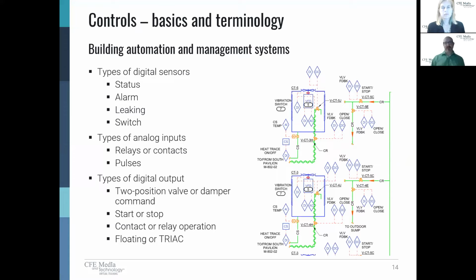It is a contact closure. Now, that's very common within our building automation system to use a variety of digital signals, a lot of digital inputs, a lot of digital outputs. On or off, yes or no. We're going to communicate with external systems with relays. But in addition, we can control solenoid valves. A solenoid valve is not partially open or partially closed, it's open or closed. We can also say start and stop. Start the motor and stop the motor. Now, if we want to control the speed of the motor, that's obviously going to be a variable type of control as opposed to a simple on or a simple off.